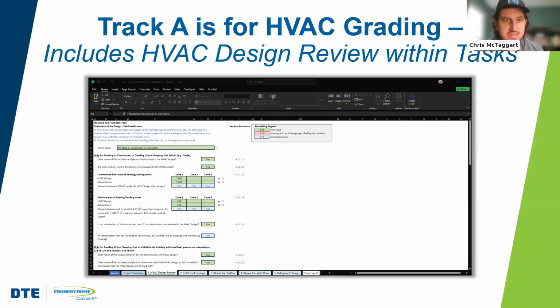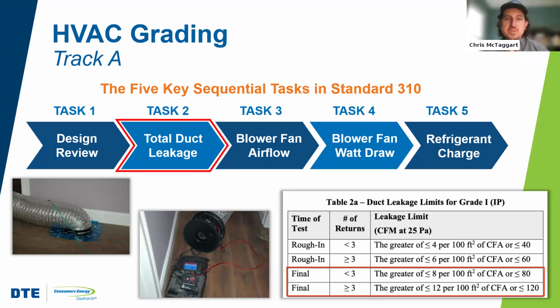All right, so design review. Again, there is a form to fill out from ResNet that the rater will fill out to document that the design review took place and that the equipment that was chosen was proper for the home and that a proper duct design was performed. Then we move to total duct leakage testing. We have to meet the total duct leakage limits as specified by Energy Star, which are at final. We'll just focus on final. If you have less than 3 returns, then 8% total duct leakage is our limit. If you have 3 or more returns, which is oftentimes typical for Michigan, where a lot of dedicated returns are utilized, 12% leakage per floor area is permitted.